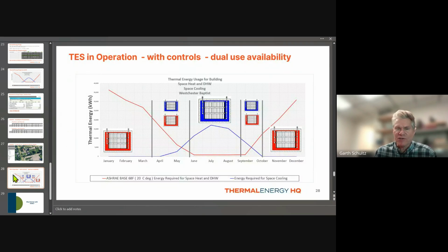As you can see from the chart, during the wintertime, using liquid, we're storing hot water, and then you come into the shoulder seasons of late spring, and sometime during the day you want space heating in the morning and then space cooling in the afternoon. We can set up the tank farm with controls and valving so that at night, during that 8-hour period when you can go and make energy, you can make some hot, you can make some cold, and address the facility throughout.